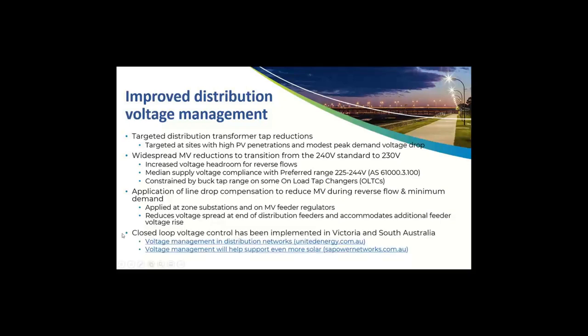A third thing that I'll touch on, that hasn't been introduced in Queensland yet but has been emerging in other states in Australia, is the use of closed loop voltage control. That uses monitoring or smart meter data at the ends of the distribution network to further dynamically adjust the voltages on the distribution network and improve the performance of the network during large reverse flows or peak demand events.